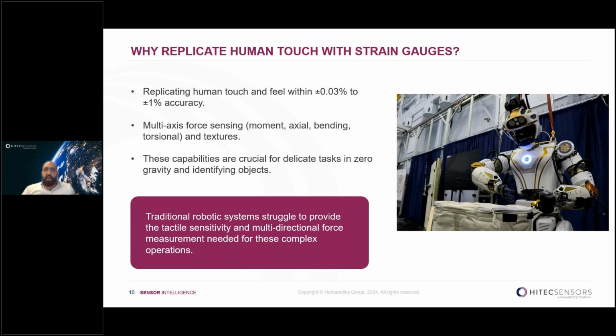Strain gauges have high sensitivity, they are flexible and precise, work well in static and dynamic environments, and have a very high resolution. Load cells provide an accuracy of approximately 0.03% to 1.1% of full-scale load. It is calculated by taking the square root of the sum of the squares divided by the number of elements, where you would be looking at hysteresis, non-linearity, creep, temperature effect, and combined error, or standard error of bias.